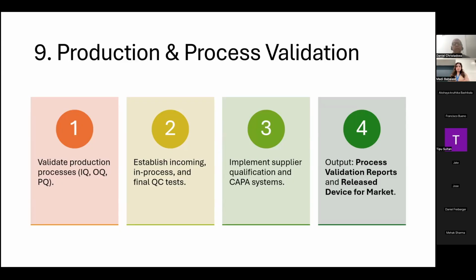The FDA does not talk about those things, because those are things you do to protect your IQ. When it comes in, before you start your IQ, if you're a good manufacturing engineer, a good process engineer, you would have done your homework, because you want to be sure that once installed, your installation qualification passes up front.